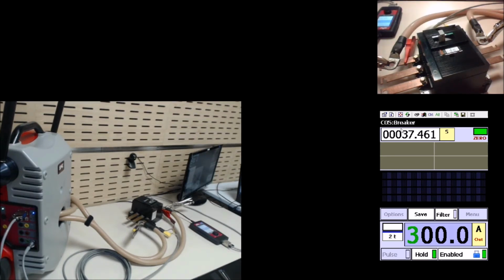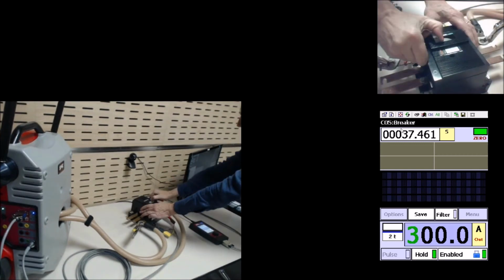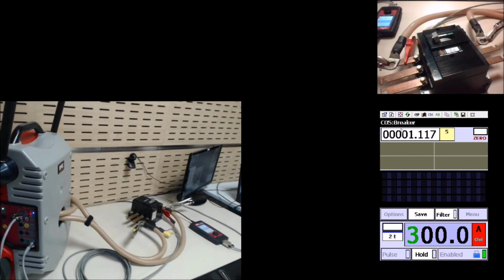If we repeat again now, now the deviation will not be as large. We won't get the half of 37, I guess. Very close to half that. So this takes us to a conclusion. Before we test the actual tripping curve of a breaker, it's recommended that you submit the breaker to a nominal current during some time, so it warms up to normal operating temperature.